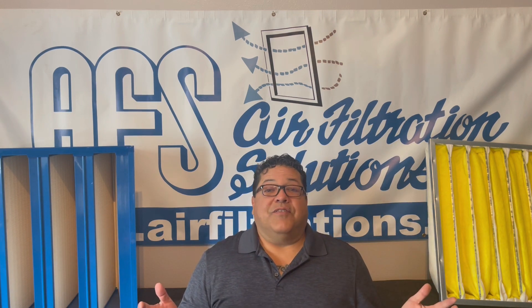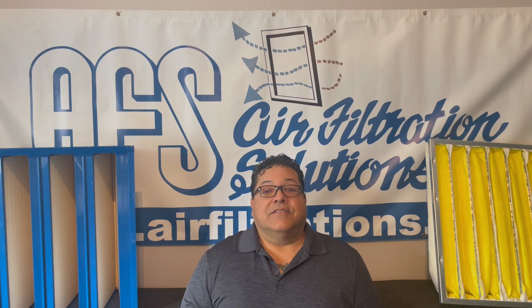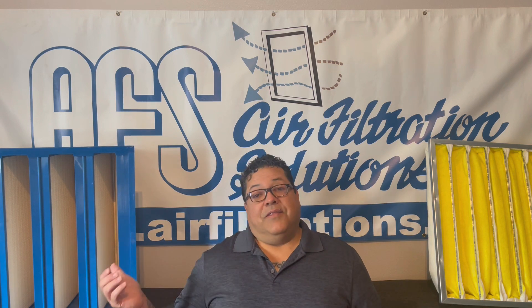I can't tell you how many times in my career I've come across final filters covered in mold. We replace them with the Fiberbond Multi Wedge 95s with Sporax, leave them in for twice the length of time — this goes 12 months, this goes 24 months — and never see any signs of mold and spores again. That's a real good indication that Sporax works, because the products before them didn't.